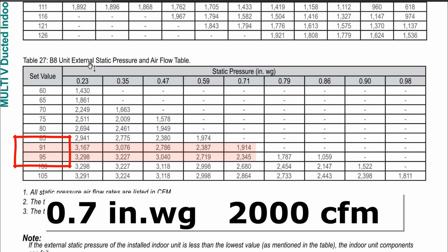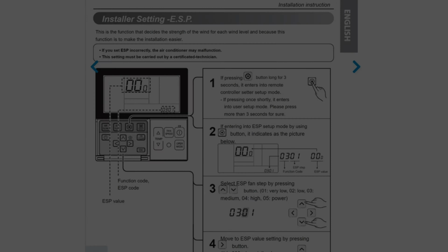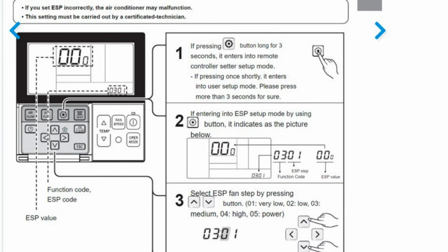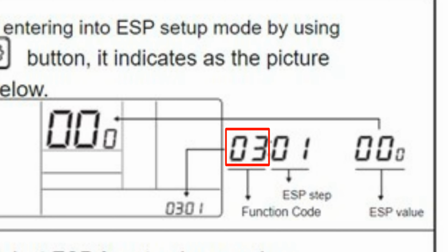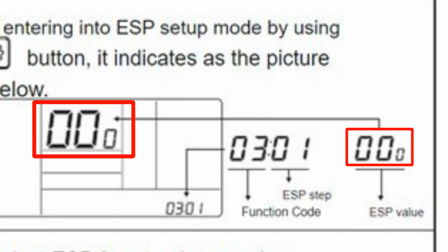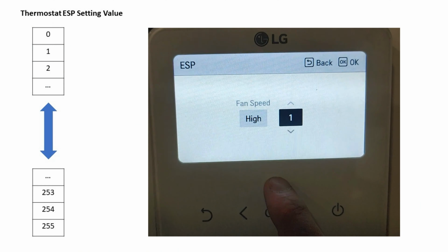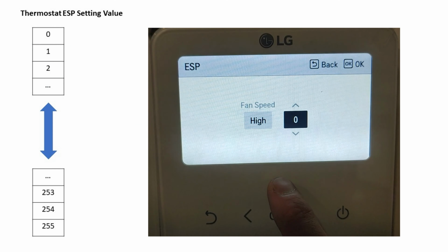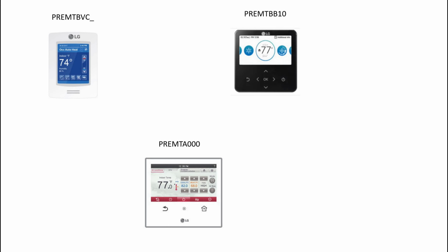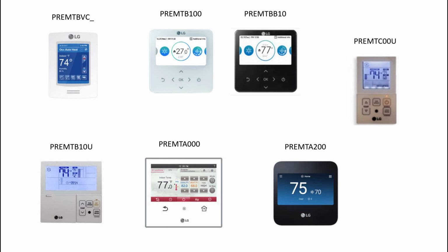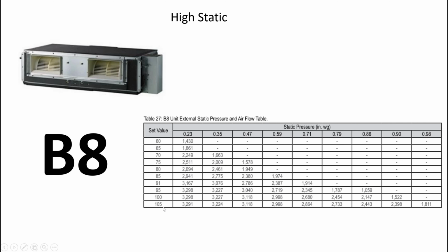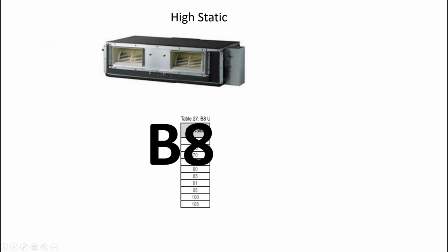Now is the most interesting part, setting of ESP. In old thermostats it's function 3. New thermostats just label it ESP, which is easier. This function has 5 ESP steps, we'll talk about it later, and an actual ESP set value. ESP settings have values from 0 to 255. LG has different types of thermostats. They are all compatible between ducted and ductless units, between commercial and residential. And they all have the option to set up ESP in a range from 0 to 255. Back to our example, B8 family units have a set value range from 60 to 105.